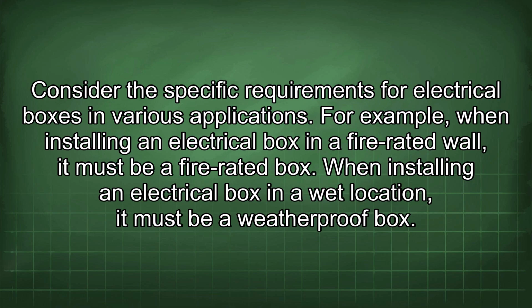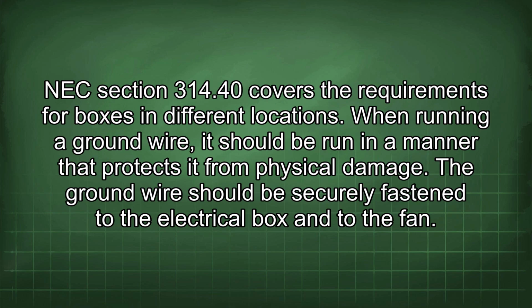Consider the specific requirements for electrical boxes in various applications. For example, when installing an electrical box in a fire-rated wall, it must be a fire-rated box. When installing an electrical box in a wet location, it must be a weatherproof box. NEC Section 314.40 covers the requirements for boxes in different locations.